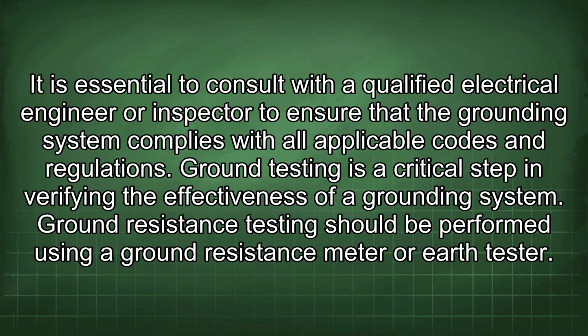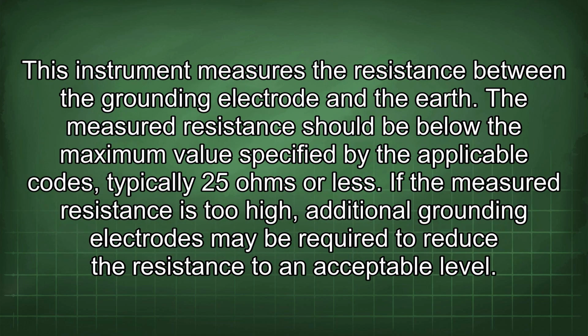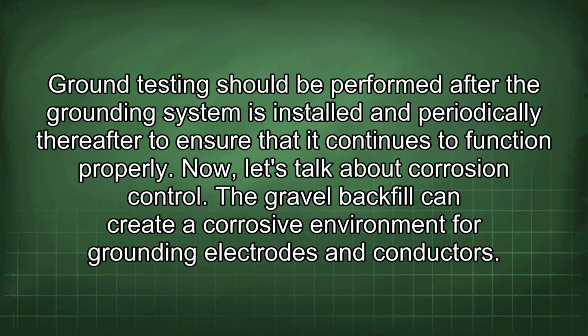Ground testing is a critical step in verifying the effectiveness of a grounding system. Ground resistance testing should be performed using a ground resistance meter or earth tester. This instrument measures the resistance between the grounding electrode and the earth. The measured resistance should be below the maximum value specified by the applicable codes, typically 25 ohms or less. If the measured resistance is too high, additional grounding electrodes may be required to reduce the resistance to an acceptable level. Ground testing should be performed after the grounding system is installed and periodically thereafter to ensure that it continues to function properly.